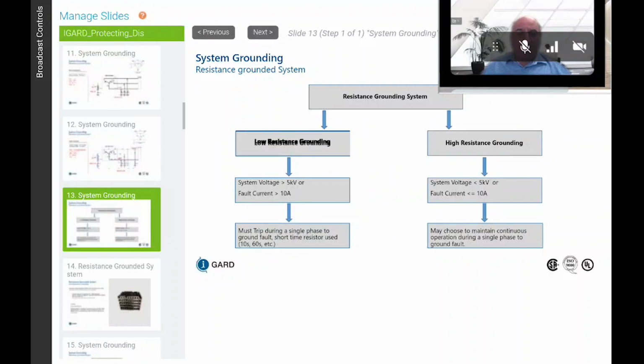So when you have a resistance grounded system, the user, the consultant, has a choice. Do we want to go with a low resistance grounded system or a high resistance grounded system? So we come up with a little flow chart here. If your system is greater than 5 kV and your charging current is greater than 10 amps, you have to use a low resistance grounded system. If your system is less than 5 kV or the charging current is less than or equal to 10 amps, you can use a high resistance grounded system.